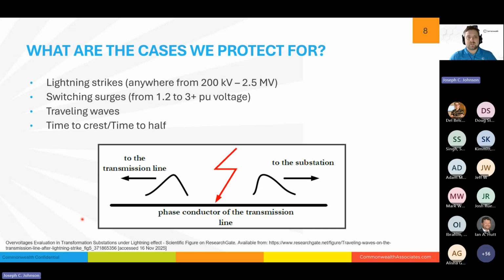When a switching surge happens, that's when a breaker opens and there's a small amount of chopping current. Even a small amount of chopping current going from something to zero almost instantly causes a very big voltage spike. Again, these are traveling waves. They propagate usually in both directions from their point of inception.